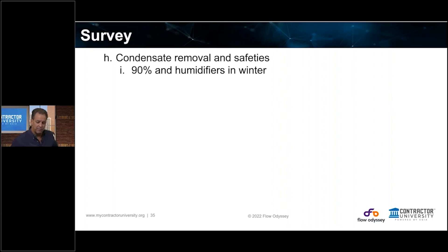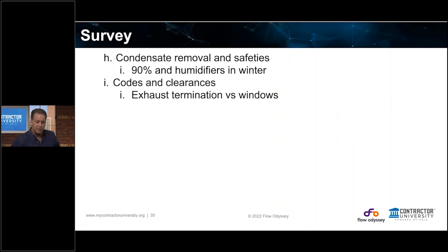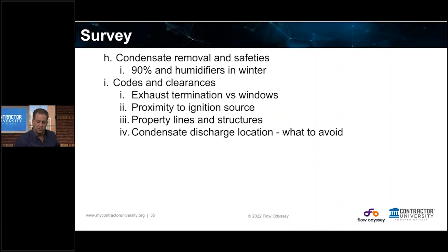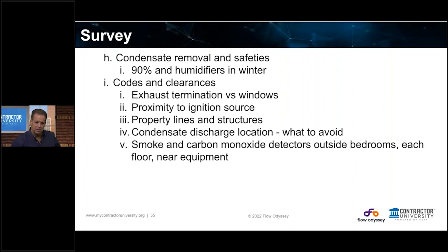Remember, we talked about 90-percenters and humidifiers in the winter — how are you going to drain those out so what you're expelling isn't freezing? You've got to make sure you're hitting all the codes and clearances. Where are you exhausting the termination of your 90-percenter? You have to be wary about window proximity, ignition sources, gas lines, and gas valves outside as well. Property lines and structures that require clearance. Condensate discharge location — you don't want to dump acidic water onto a sidewalk or patio. I've seen companies that had to buy whole new stamped concrete patios because of acidic condensate discharge.